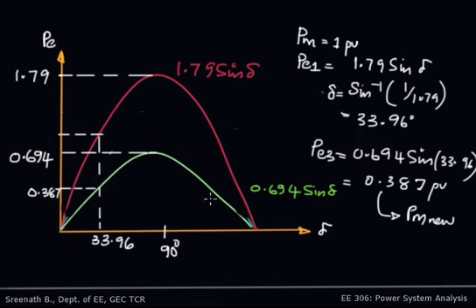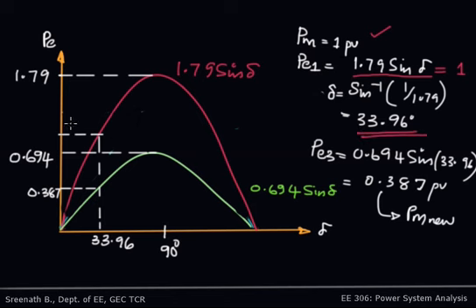Initially, one per unit of power is being generated and transferred. The healthy condition equation Pe1 = 1.79 sin δ can be equated to 1, since Pe1 = Pm under normal operation with losses neglected. This gives the initial rotor angle delta = 33.96 degrees. Now consider what happens when the fault occurs.